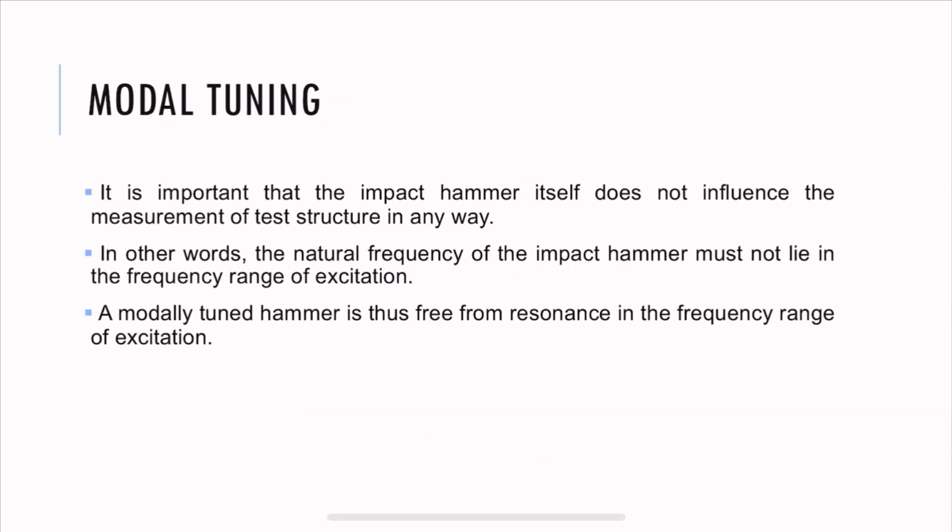Now, there is one important thing when you're performing this experiment. It's called modal tuning. It's important that the hammer itself doesn't influence the measurement of the test structure in any way. Like every other structure, each structure is going to have its own natural frequency, and this modal hammer is no exception. It's also going to have its own natural frequency. So this natural frequency should not lie in the frequency range of excitation.